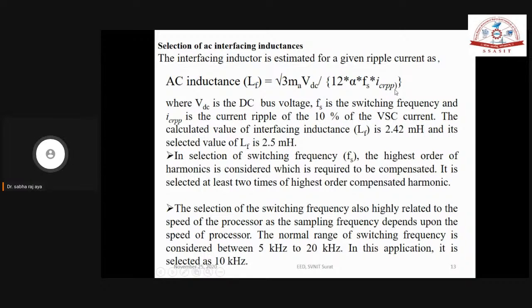I_CRPP means how much percentage of distortion you are going to allow on the compensating current. It is the percentage ripple on the compensating current, the ripple at the harmonic frequency. Suppose you are going to allow 10% distortion on the compensating current, 10% distortion on the compensating current. Generally, people take 10 to 25%.